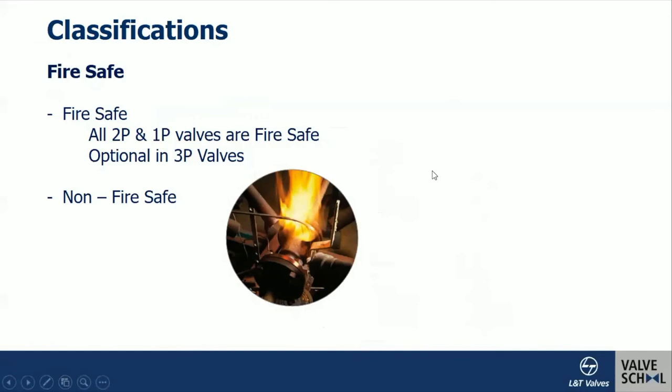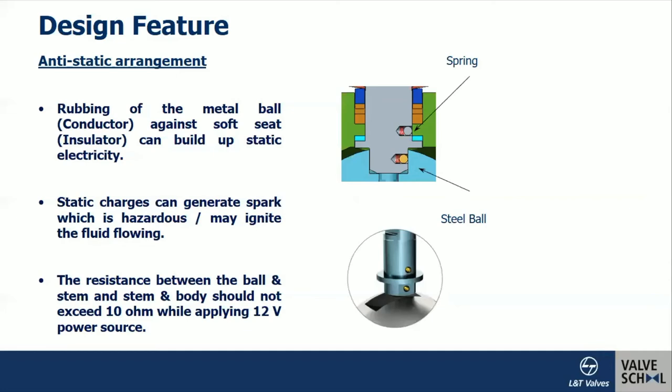Another classification is fire-safe versus non-fire-safe. Metal-seated valves are intrinsically fire safe. For soft-seated valves, there is a necessity that in the event of external fire, the soft component may be sublimated or extinguished by external heat. The question is whether the valve will still seal to prevent flow beyond that point. Fire-safe qualification testing is performed as per API 607 and ISO 10497.